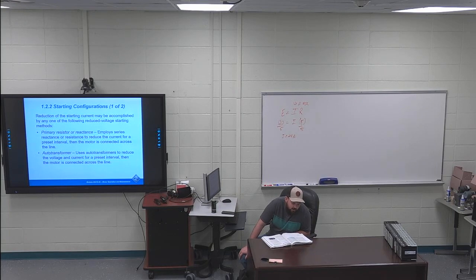Part winding starting involves motors with 2 separate winding circuits. So we'll start on one circuit and then run on another. That's highlighted. Then 1, 2, 3 insulation systems. I have 4 highlights on the right hand side of page 6. I've got Class A highlighted, first sentence. Class A insulation systems have a suitable thermal endurance when operated at the limiting Class A temperature of 105 degrees Celsius. I've got Class B, first sentence highlighted.